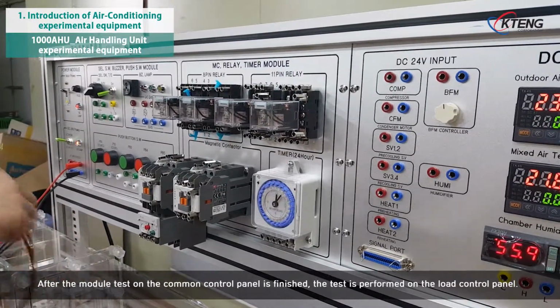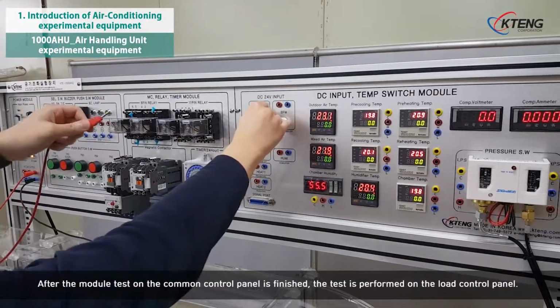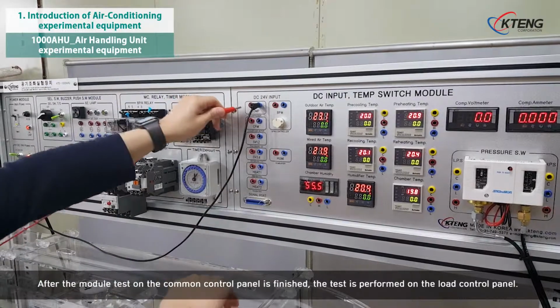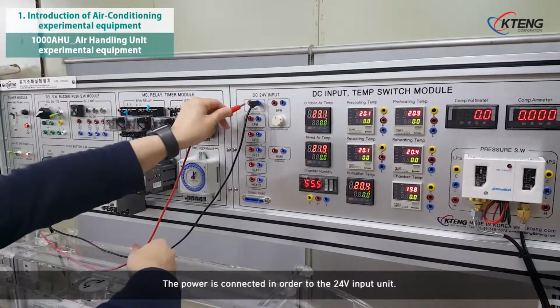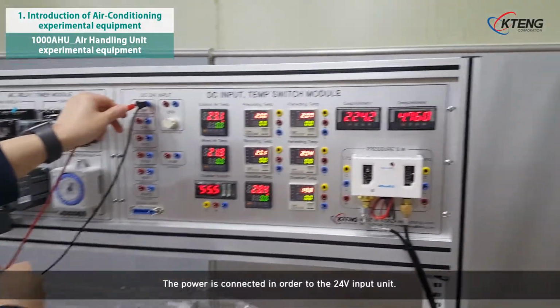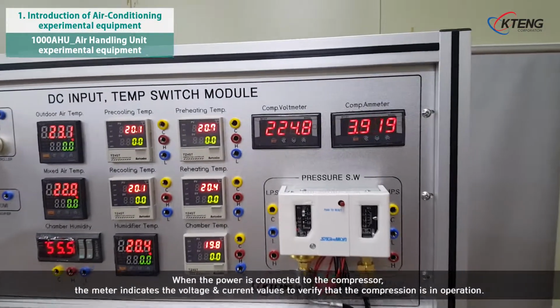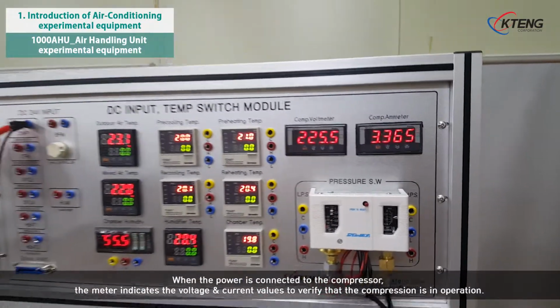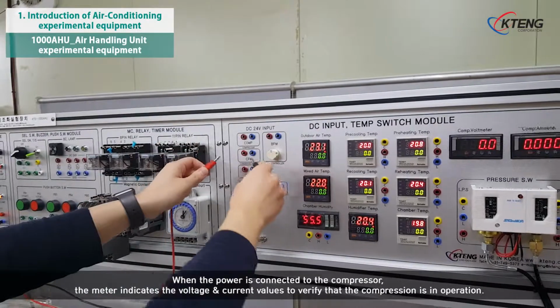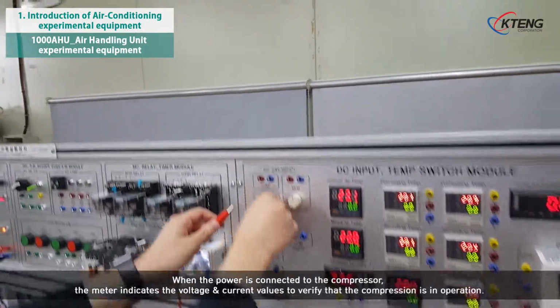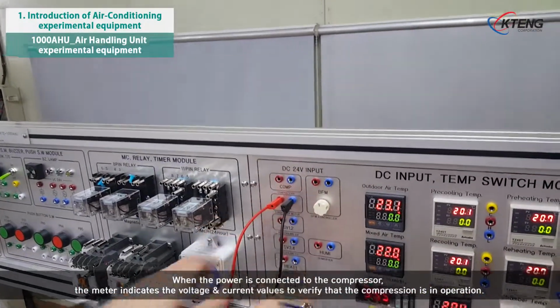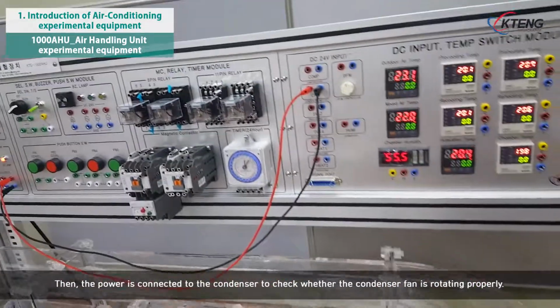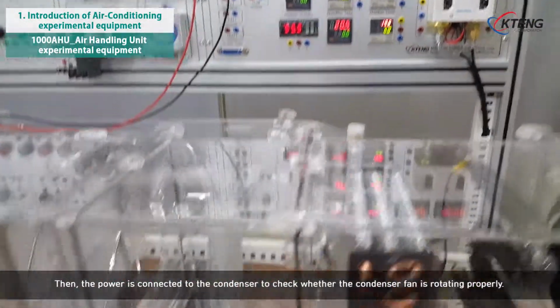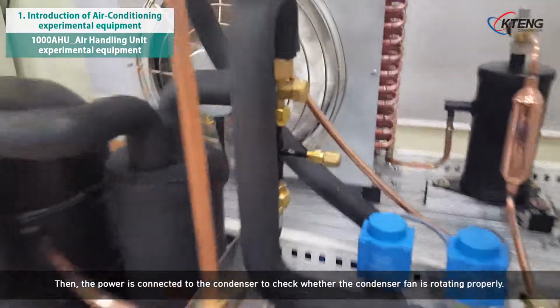After the module test on the common control panel is finished, the test is performed on the load control panel. The power is connected in order to the 24-volt input unit. When the power is connected to the compressor, the meter indicates the voltage and current values to verify that the compression is in operation. Then, the power is connected to the condenser to check whether the condenser fan is rotating properly.